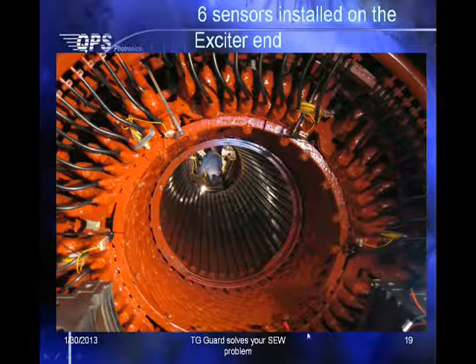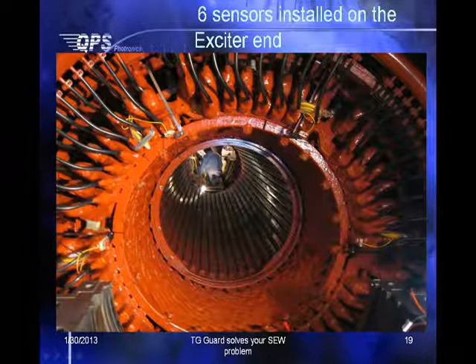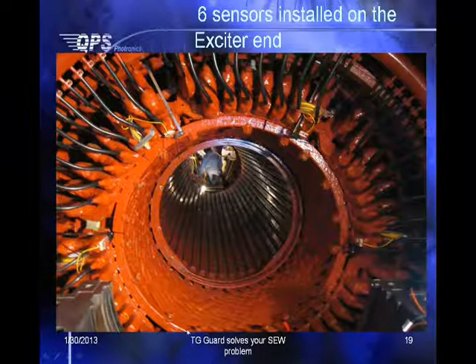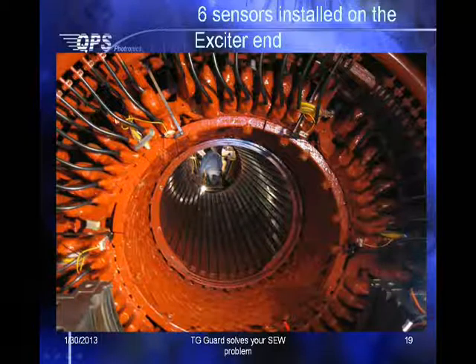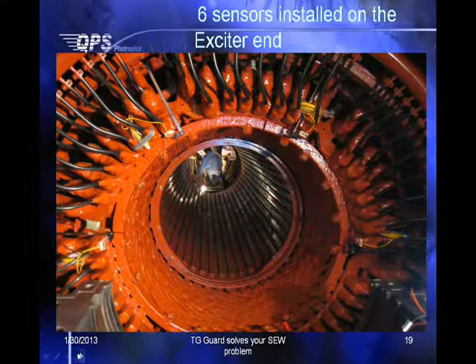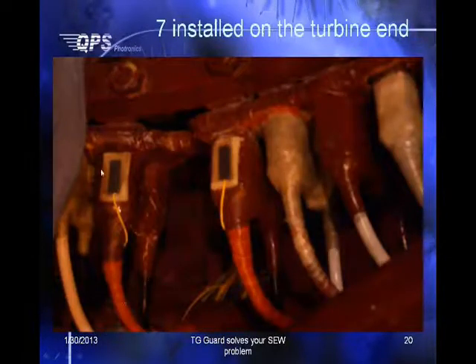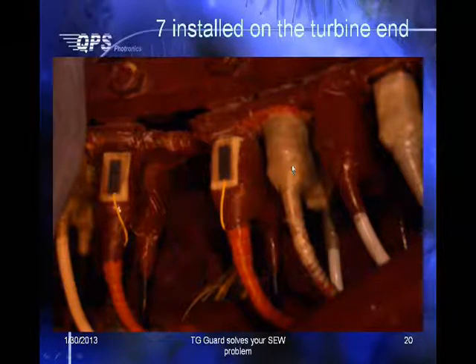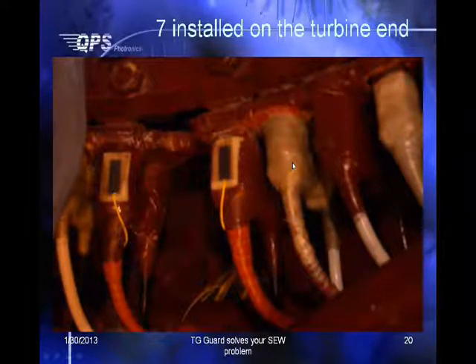All the sensors are now installed the same way, with 6 on one end, you see the cables running, and then on the other end we put 7. At the customer's request, one of the sensors was actually installed directly on the copper conductor, because our sensor is non-conducting, so this is perfectly safe.